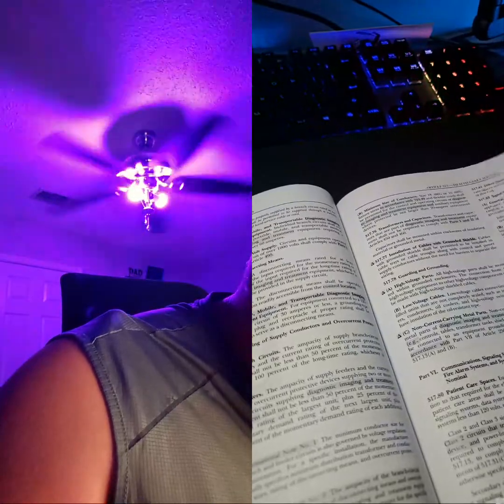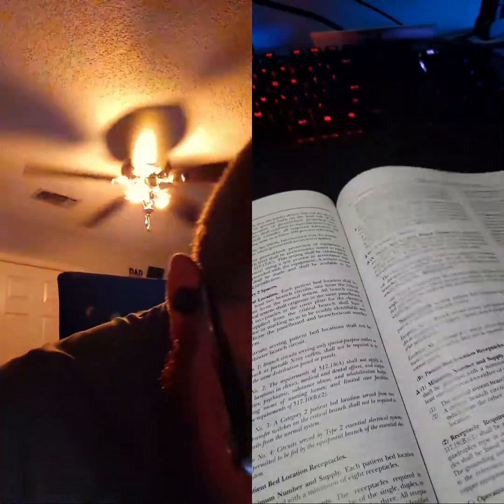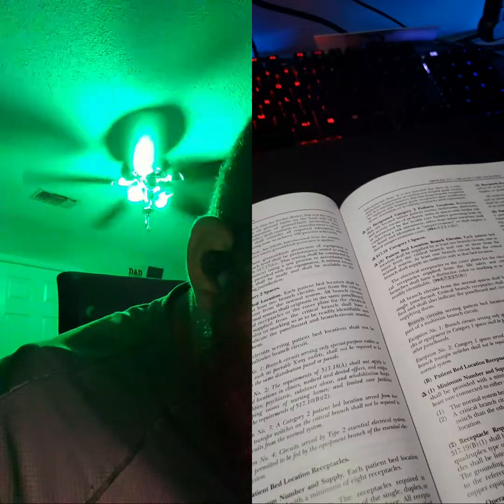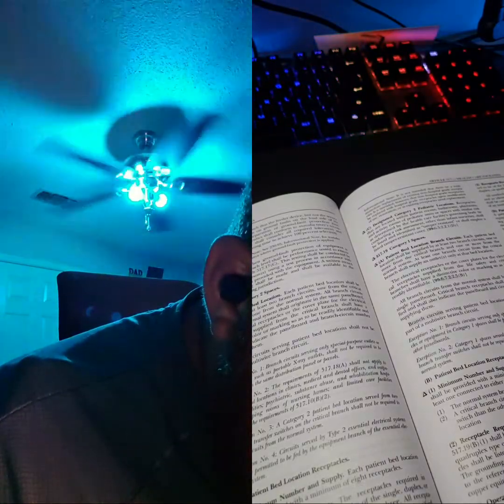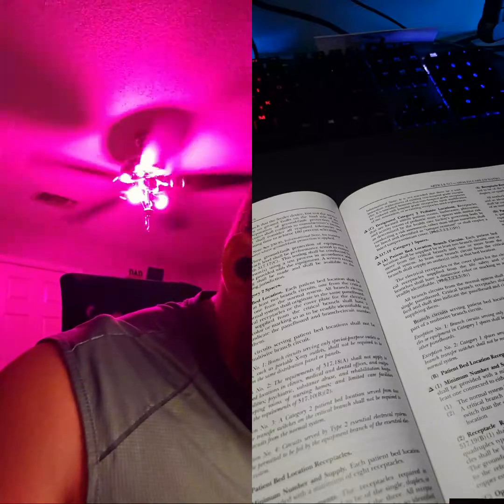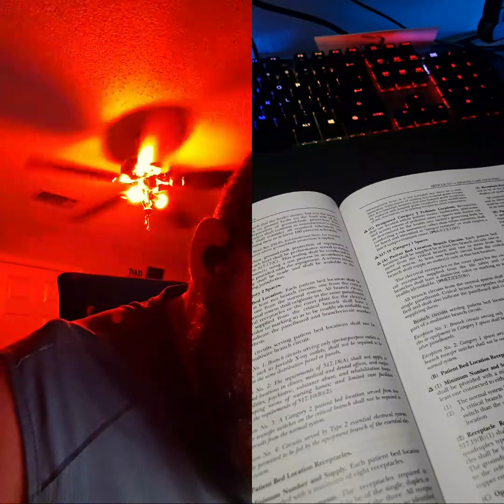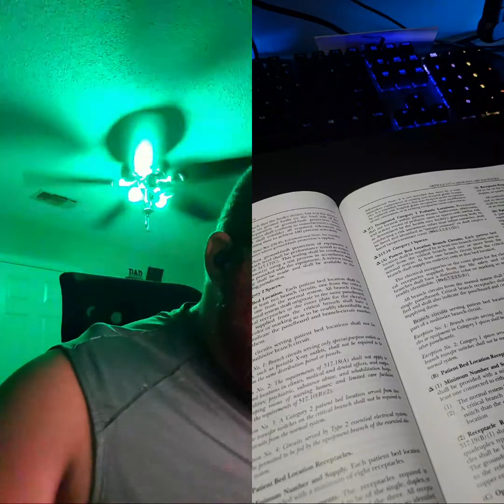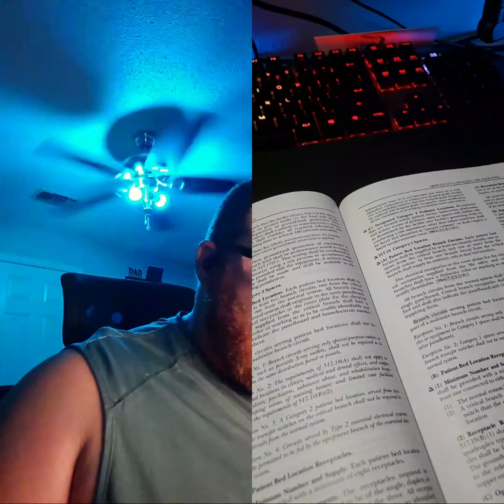And then let's look for the word life safety. And it has to do with either automatic doors used for building egress or illumination of electrical equipment rooms. So we know 517.32. We've both done hospitals. Typically the life safety, the yellow circuit, that's usually your lighting, right? Well, no. But also your critical. I thought it was orange. How important is it to illuminate an electrical equipment room? Very important.